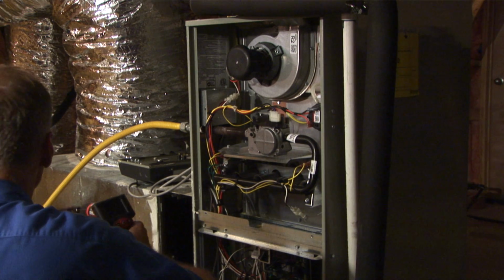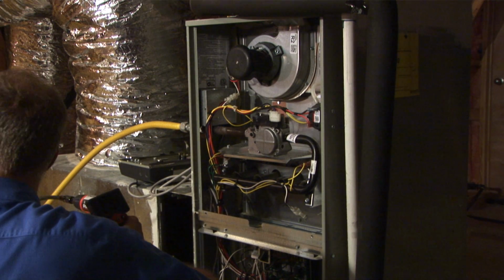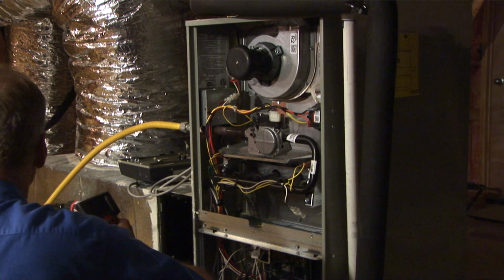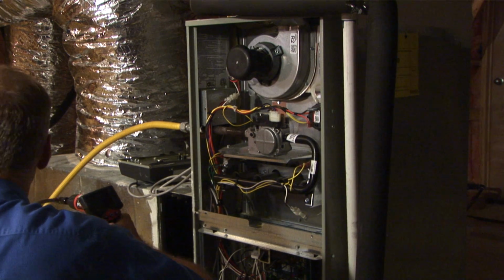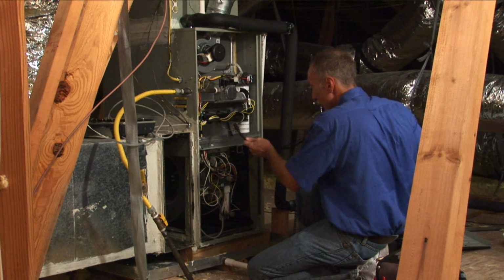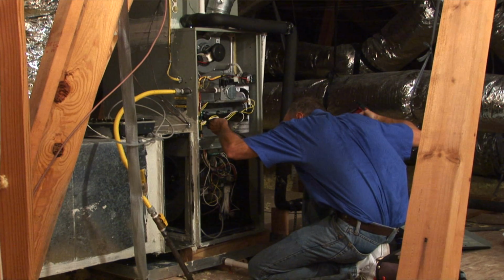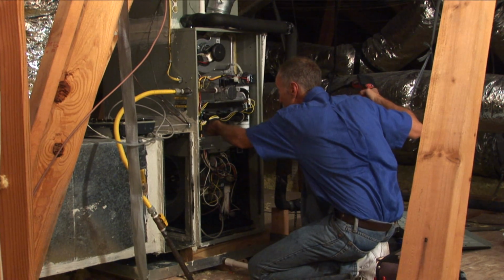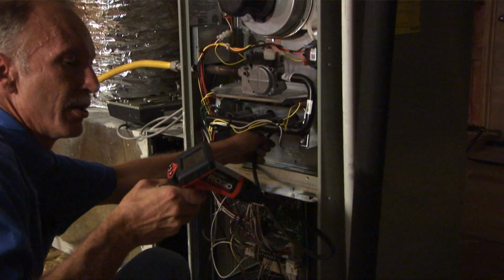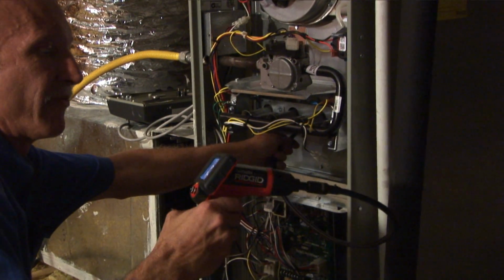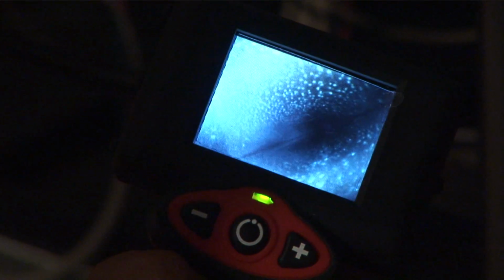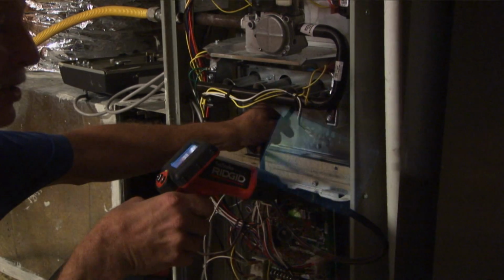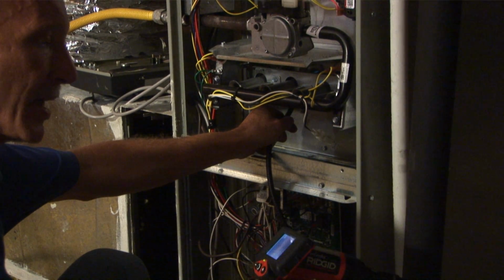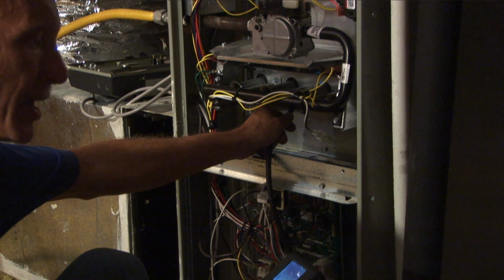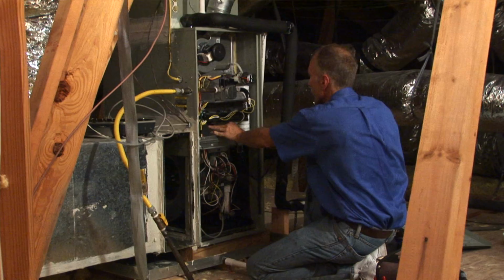The next part of the inspection is to visually check the heat exchanger for cracks. I'll do so with the telescopic scope that I will insert into the heat exchanger. As I do that, I will be viewing the camera and checking for cracks. As I can see, this heat exchanger again is in excellent condition.